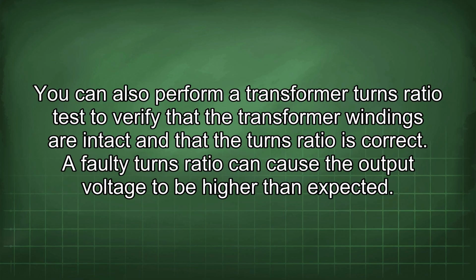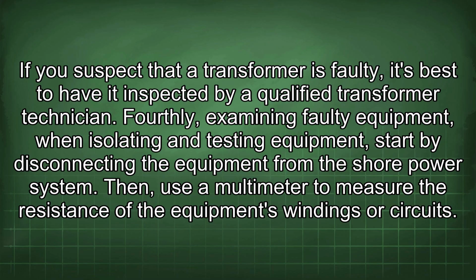You can also perform a transformer turns ratio test to verify that the transformer windings are intact and that the turns ratio is correct. A faulty turns ratio can cause the output voltage to be higher than expected. If you suspect that a transformer is faulty, it's best to have it inspected by a qualified transformer technician. Fourthly, examining faulty equipment. When isolating and testing equipment, start by disconnecting the equipment from the shore power system.